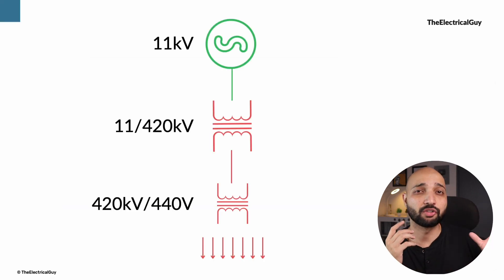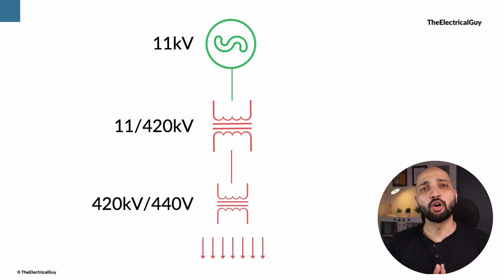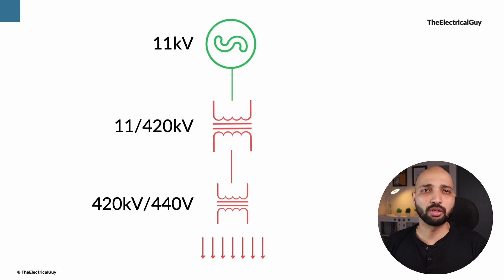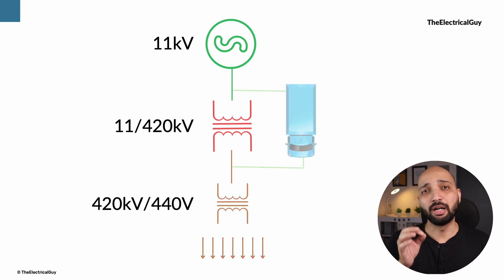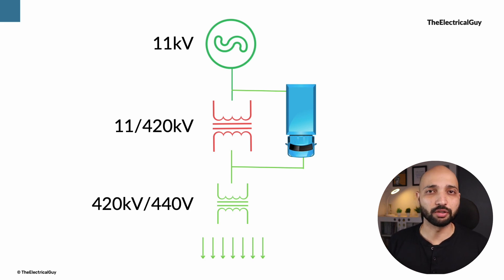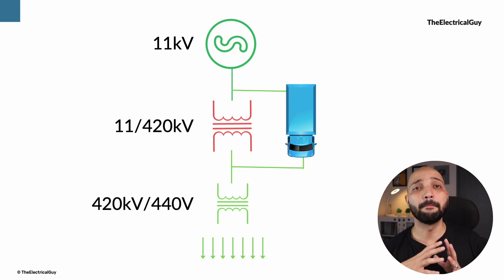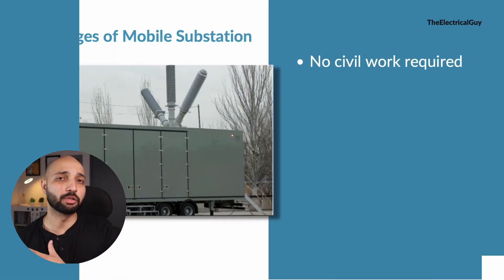Going back to our example where the step-up substation went off for maintenance lasting around two months — instead of keeping the supply off and incurring losses, I can get a mobile substation, bypass the substation under maintenance, give supply via the mobile substation, and continue with the supply. In this way I am not having losses — my main substation is under maintenance but supply continuity is maintained and I am still earning tariff charges.